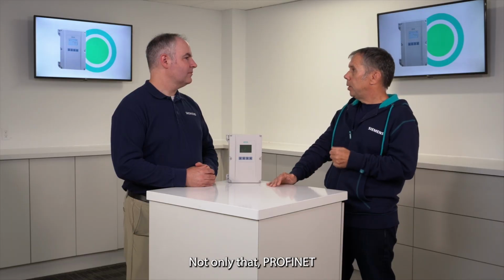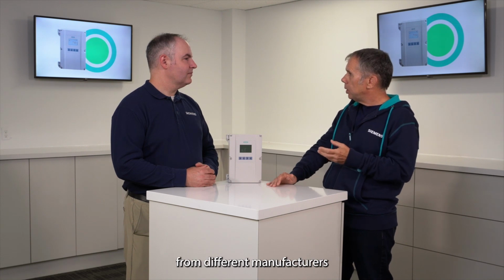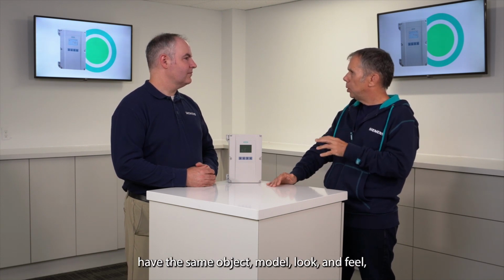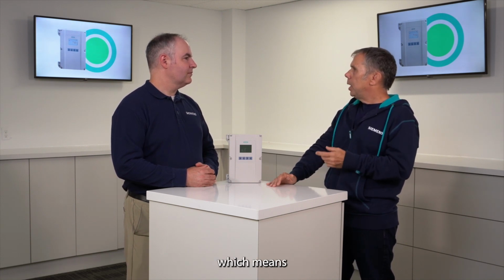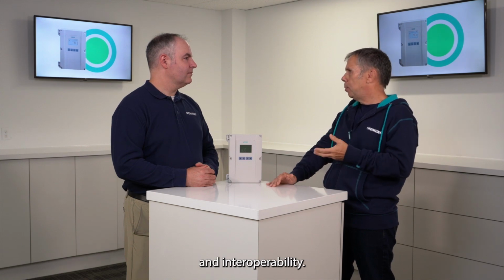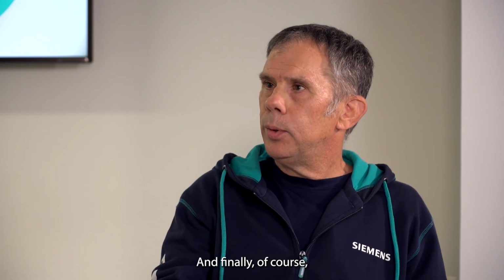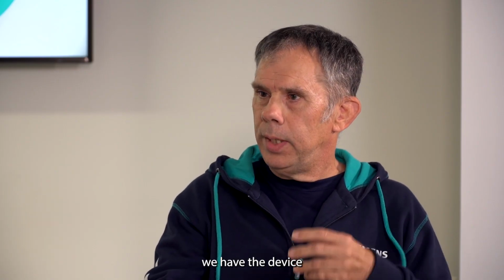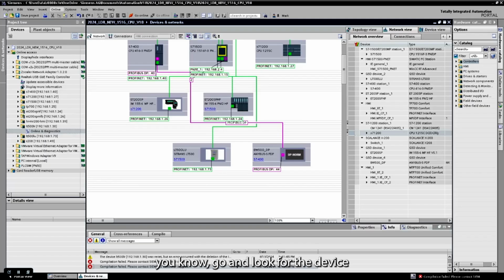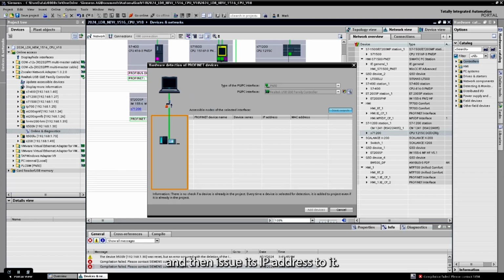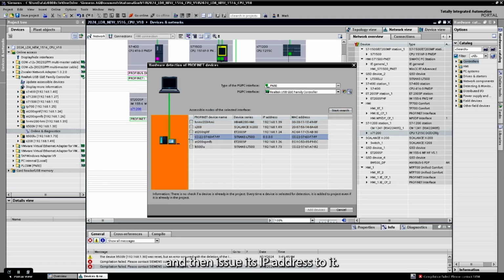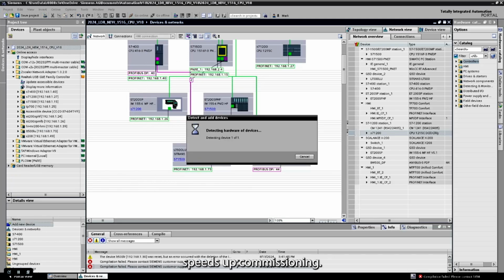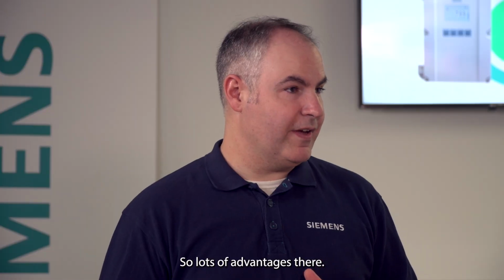Not only that, Profinet also supports a profile standard, so devices from different manufacturers have the same object model look and feel, which means great interchangeability and interoperability. And finally, of course, with Profinet, the device I/O controller will go and look for the device on the network by its network name and then issue its IP address to it, so it drastically speeds up commissioning. So lots of advantages there. Now, what can you tell me about Ethernet IP?